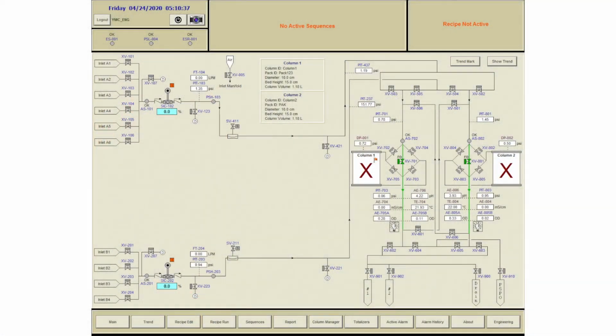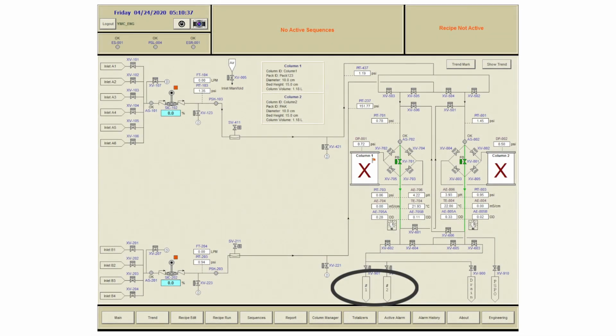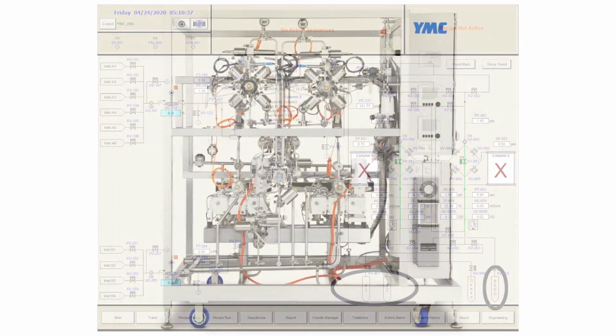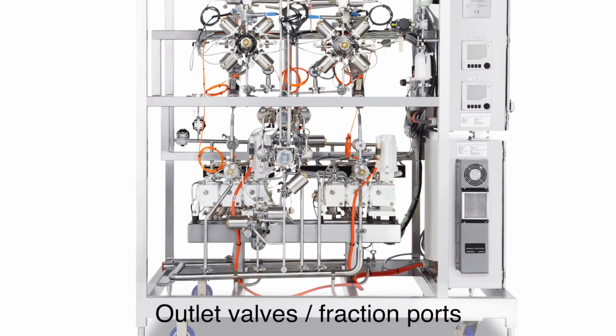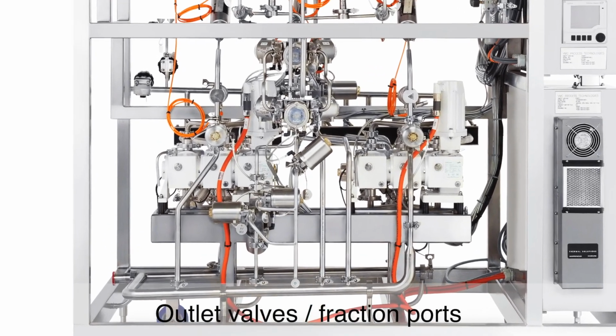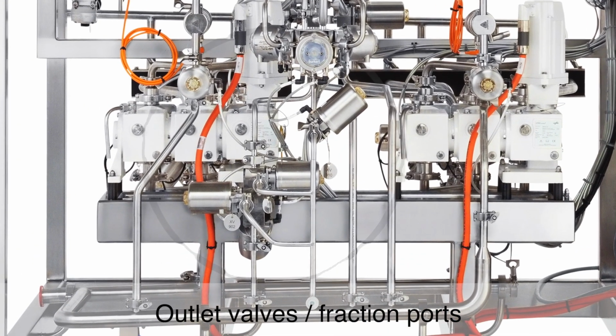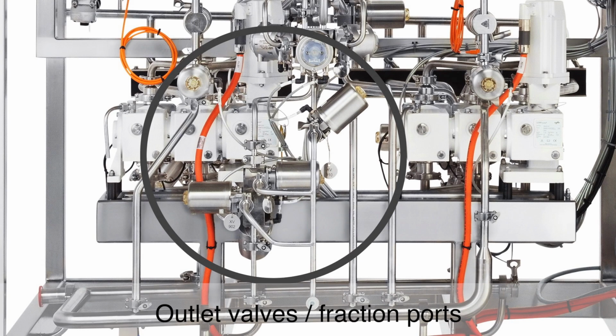Completing our walkthrough of the fluid hardware side of the unit, the system is also equipped with parallel outlets. One is a single valve and the other is a fractionation valve. On the system, the outlet valves are located near the outside of the frame. The system shown here has only two fraction ports. However, there is an option to have up to 5 fraction ports.